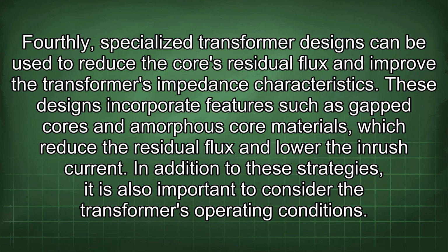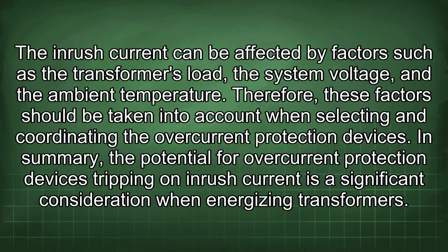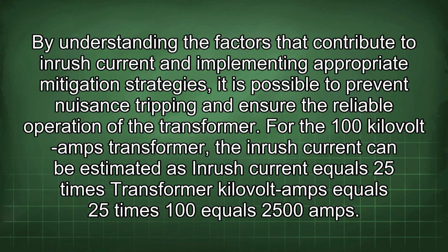In addition to these strategies, it is also important to consider the transformer's operating conditions. The inrush current can be affected by factors such as the transformer's load, the system voltage, and the ambient temperature. Therefore, these factors should be taken into account when selecting and coordinating the overcurrent protection devices. In summary, the potential for overcurrent protection devices tripping on inrush current is a significant consideration when energizing transformers. By understanding the factors that contribute to inrush current and implementing appropriate mitigation strategies, it is possible to prevent nuisance tripping and ensure the reliable operation of the transformer.